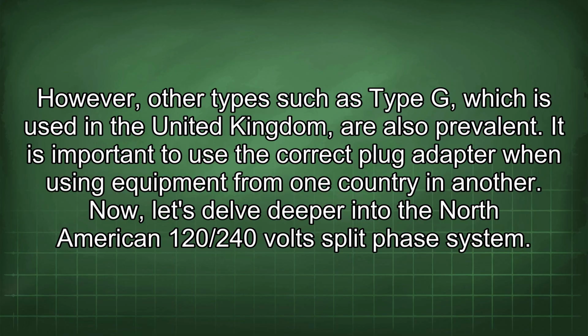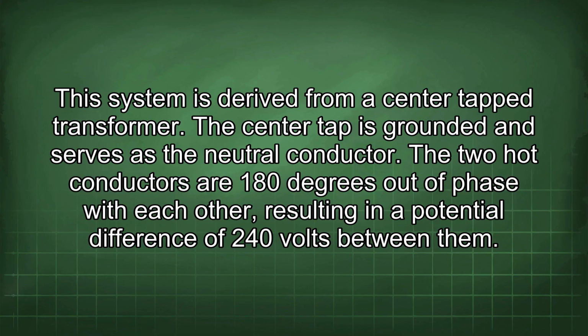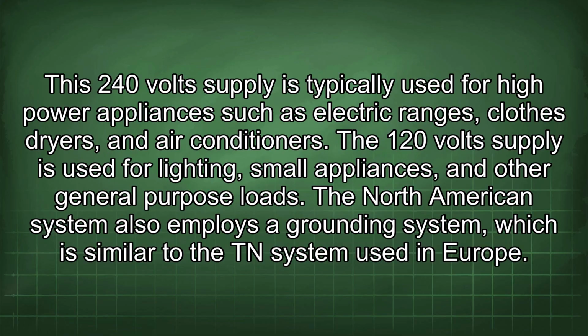Now, let's delve deeper into the North American 120/240 volt split-phase system. This system is derived from a center tap transformer. The center tap is grounded and serves as the neutral conductor. The two hot conductors are 180 degrees out of phase with each other, resulting in a potential difference of 240 volts between them. This 240 volt supply is typically used for high power appliances such as electric ranges, clothes dryers, and air conditioners. The 120 volt supply is used for lighting, small appliances, and other general purpose loads.